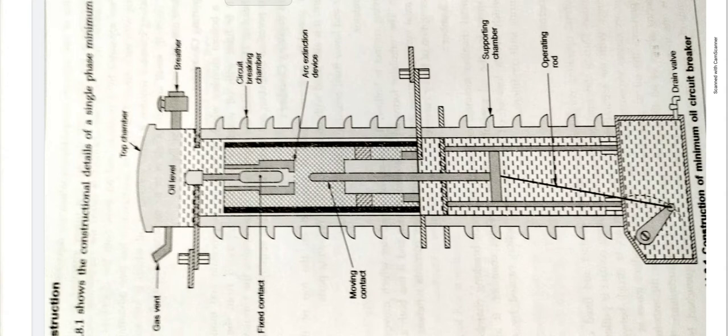During abnormal conditions, the moving contact is pulled down by the tripping springs with the separation of contacts and arc is struck between them. Then, the energy in the arc causes vaporization of oil. This will produce gases at high pressure.